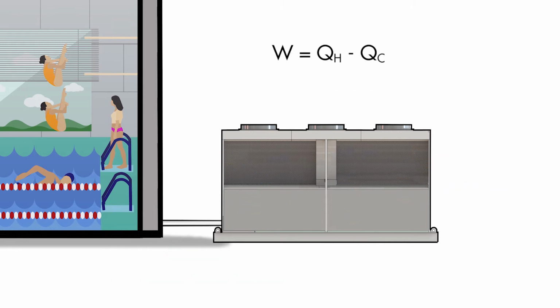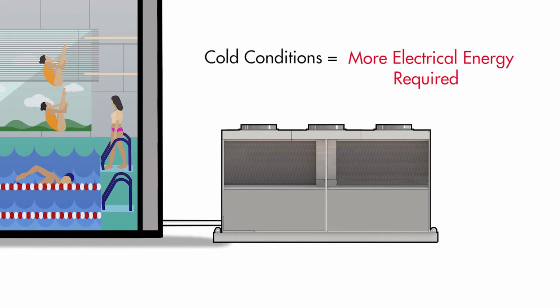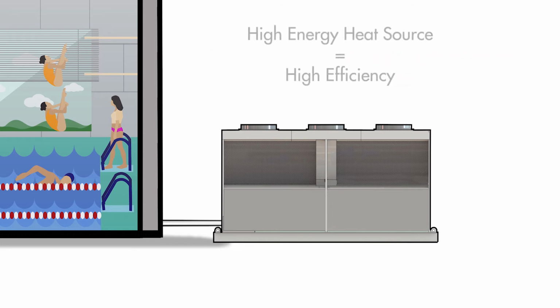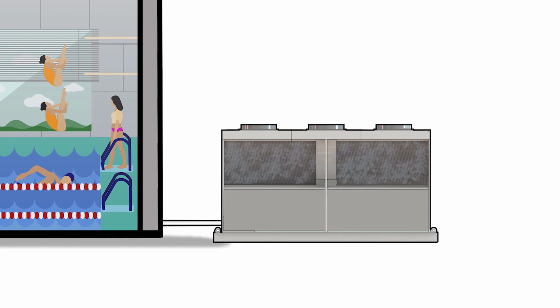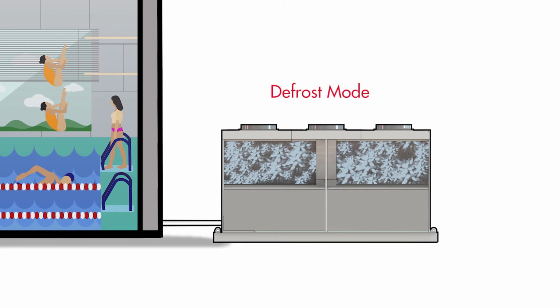This is because the work done is directly proportional to the difference in energy between the heat source and heat sink. As the heat pump needs to work harder, efficiency is lost, and more electrical energy is required to provide the necessary heating. Clearly then, using air with the highest energy level as the heat source results in the most efficient solution. Further, there is a secondary problem in cold ambient conditions. If the evaporating temperature falls below zero, moisture in the air freezes on the coil, forcing the heat pump to intermittently go into defrost mode and stop providing heat.